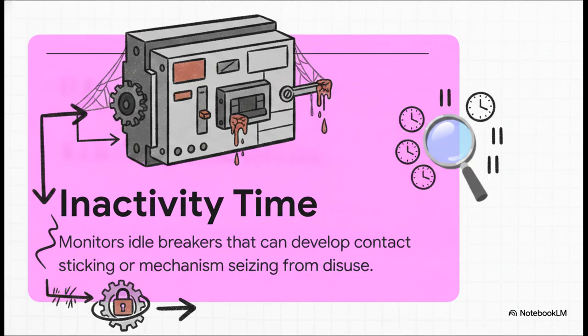And then we have inactivity time. What people often miss here is the paradox of nothing happening. We intuitively feel that if a breaker is just sitting there doing nothing, it's safe, it's in a stable state. But prolonged idleness is itself a severe degradation risk. Over time, those mechanical lubricants can dry out, and the complex mechanisms can literally stick together from disuse. If you aren't monitoring inactivity, you might command a breaker to trip after 2 years of silence, only to find it's completely seized up. No way do you want that.